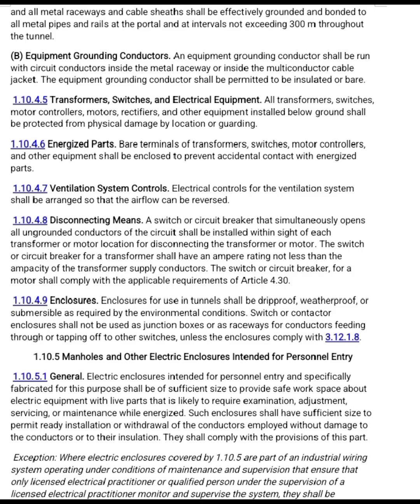Exception: where electrical enclosures covered by 1.10.5 are part of an industrial wiring system operating under conditions of maintenance and supervision that ensure that only a licensed electrical practitioner or qualified person under the supervision of a licensed electrical practitioner monitors and supervises the system, they shall be. This indicates equipment grounding conductors or grounding wire must be installed together with circuit wires inside the metal conduit or cable. This grounding wire can be insulated or bare.